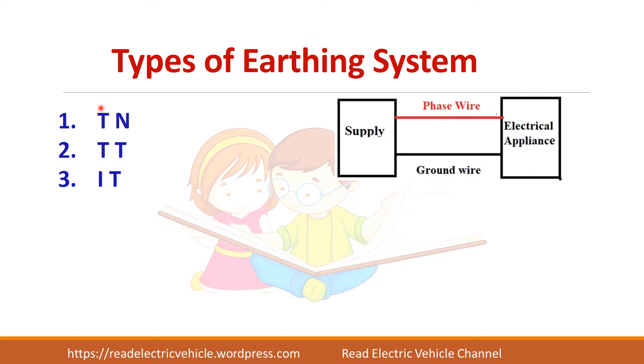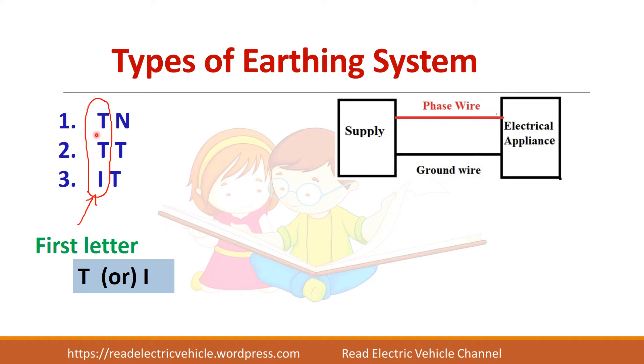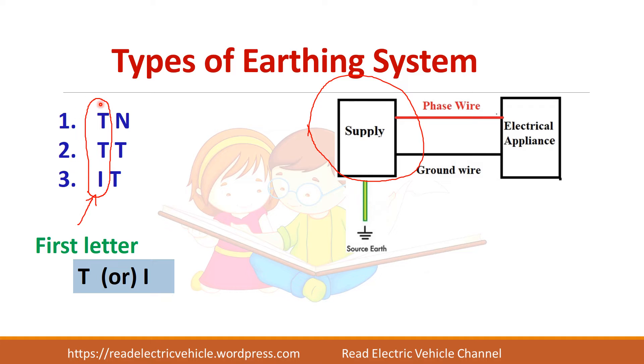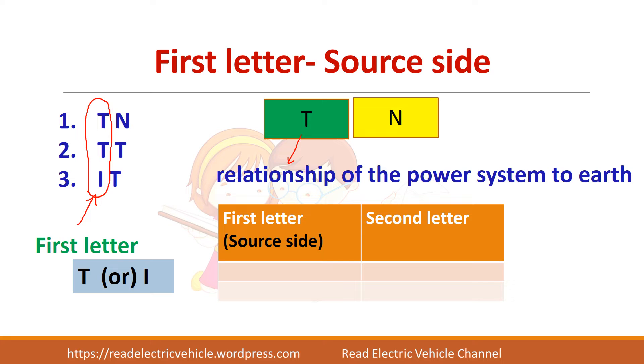Looking at the first letter in all three cases, it is either T or I. T represents earth or land, and I means isolated — that is, isolated from the earth. The first letter represents how the source is connected to the earth: whether it is connected to earth or isolated from earth. For the first letter, T means a direct connection of the source to the earth, while I means all live parts on the source side are isolated from the earth.